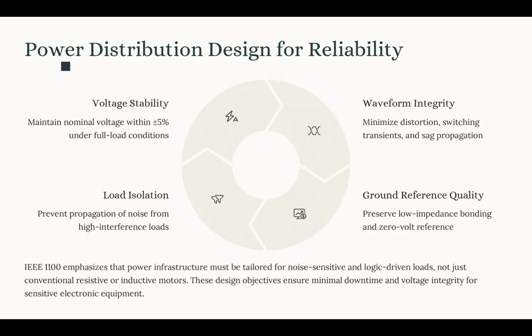Now, there are four key design objectives based on the IEEE 1100. One would be the voltage stability. We mentioned there is criteria to maintain the nominal voltage within plus minus 5%, and it is under full load condition. Please note that. We have waveform integrity as a criteria for power distribution, which basically means the total harmonic distortion and zero crossing distortion should be limited based on the criteria defined in the IEEE 1100 and IEEE 519.